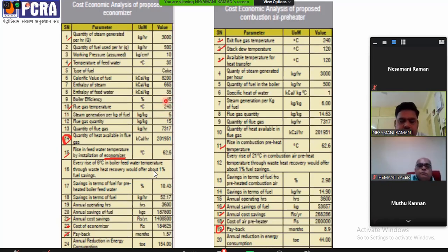What is the constraint to reducing the temperature? It is only sulfur corrosion. So taking that into consideration, we have to reduce the flue gas temperature by implementing an economizer. They could achieve a rise in feed water temperature through the economizer to 62 degrees Celsius. So it had energy savings of almost 14 lakhs per annum. The cost of the economizer was 1.8 lakhs. So payback was less than 2 months.